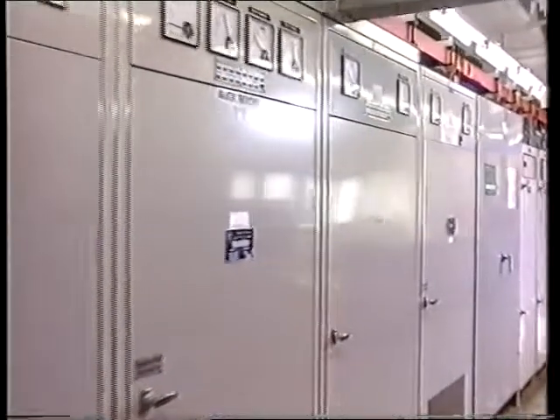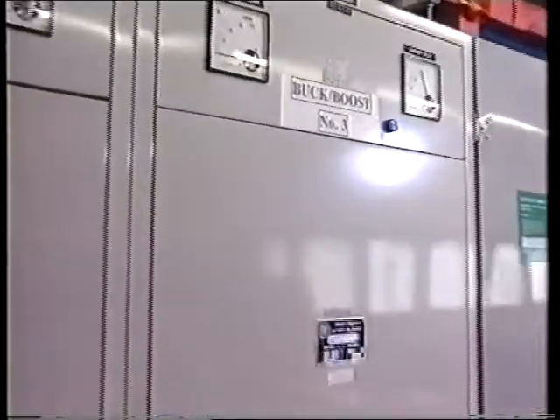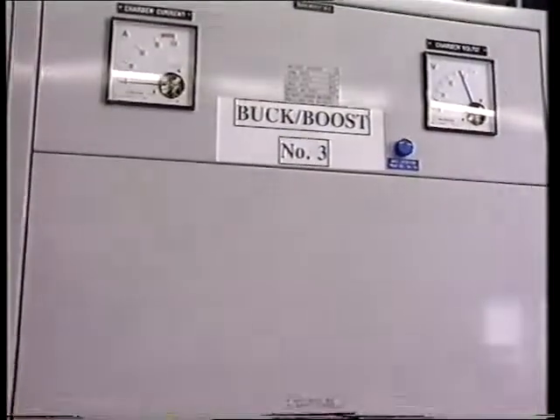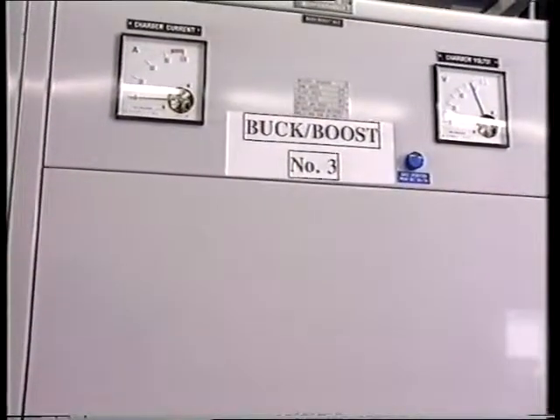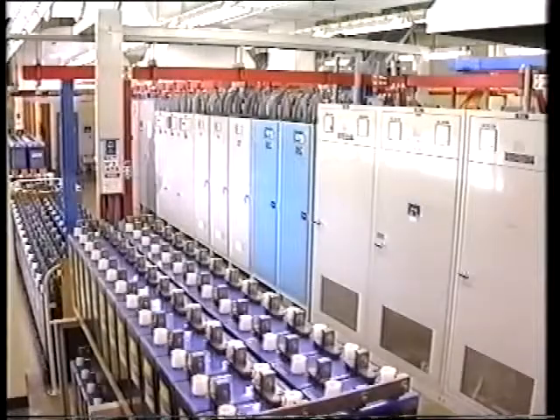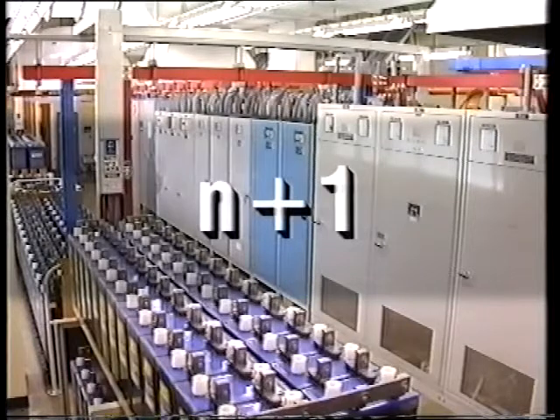An operational buck-boost power supply system may consist of a number of units of either capacity or a combination of both, as shown here. As with integrated power suites, buck-boost systems are provided on an N+1 basis, that is, with one unit available for redundancy.